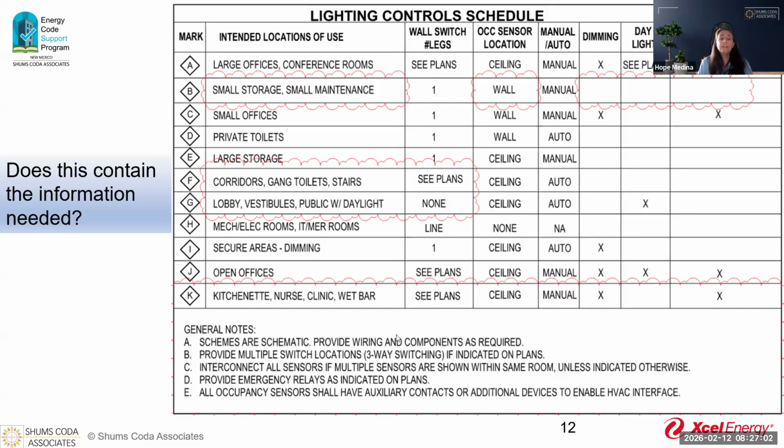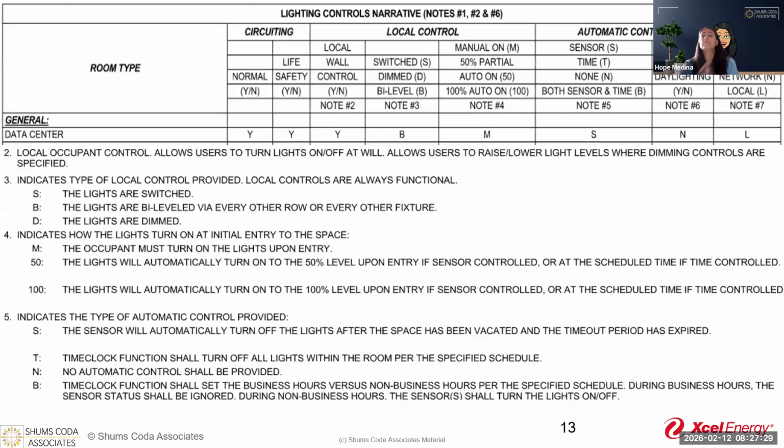So when I look at this, I'm thinking, all right, they met the criteria as far as ensuring that they have it. So this is their lighting control schedule, but it's not their sequence of operations, right? Because they all have different things. Is it shutting completely off? Is it only 50%?